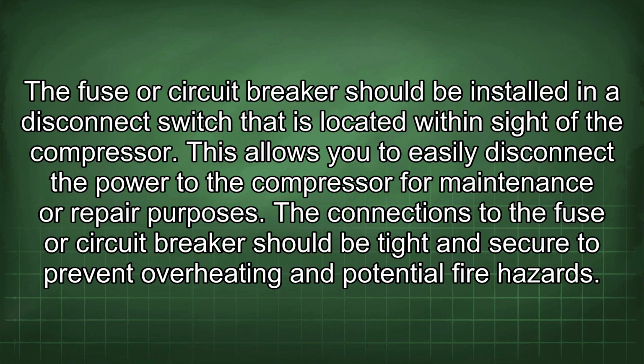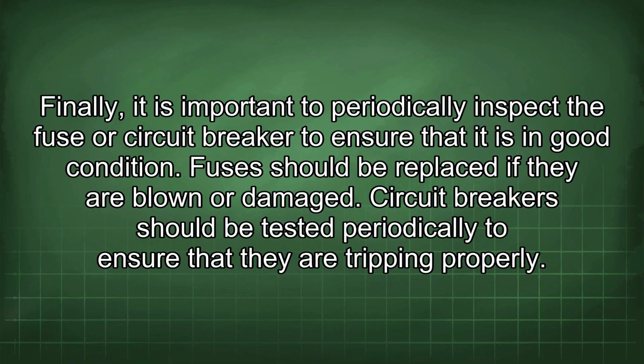This allows you to easily disconnect the power to the compressor for maintenance or repair purposes. The connections to the fuse or circuit breaker should be tight and secure to prevent overheating and potential fire hazards. Finally, it is important to periodically inspect the fuse or circuit breaker to ensure that it is in good condition. Fuses should be replaced if they are blown or damaged.